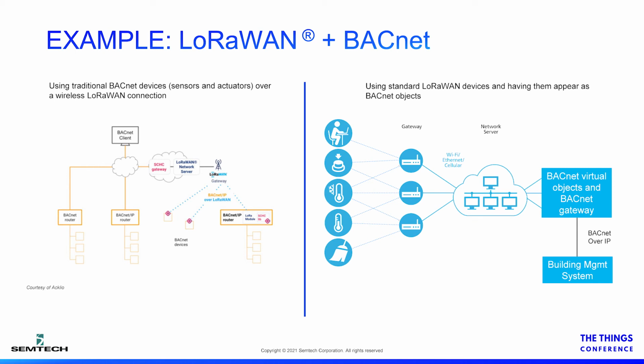This system manages a BACnet over IP network. In this case, the LoRaWAN network is set up and maintained completely separately from the BACnet network with a single gateway, presenting the devices as BACnet virtual objects to the BACnet network.